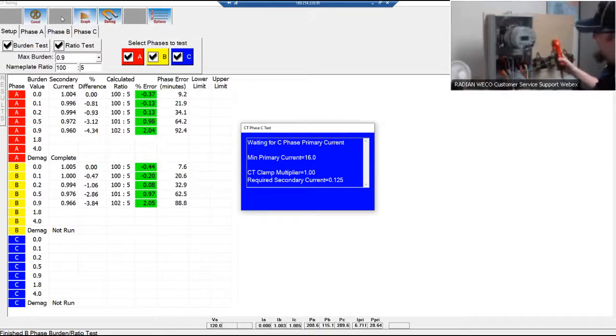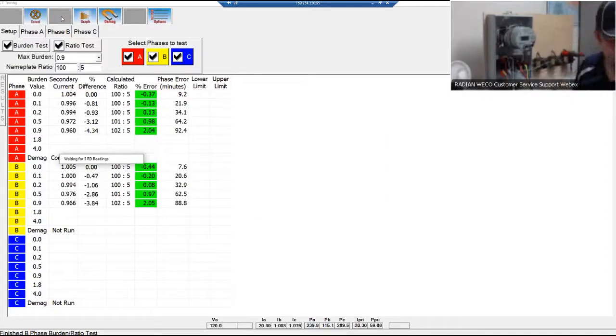Something I want to show off real quick is the RW will tell you if you have this probe on backwards, or if it believes you have the probe on backwards. So this time, instead of hooking it up correctly, I'm going to flip this probe 180 degrees out. So now I've put it on backwards. And you'll see the RW is going to yell at me in a second.